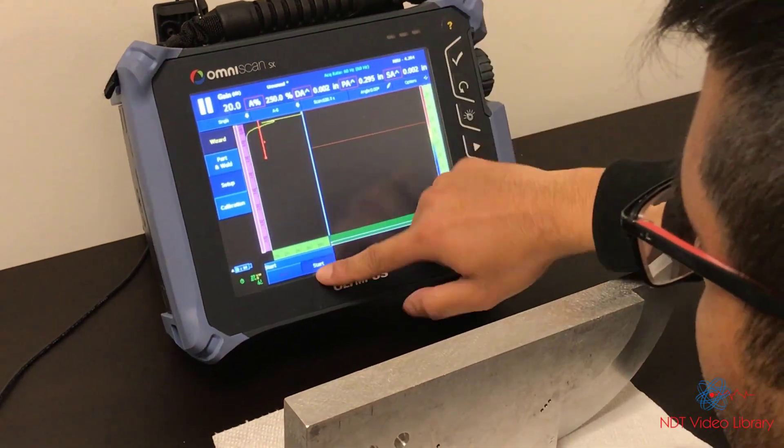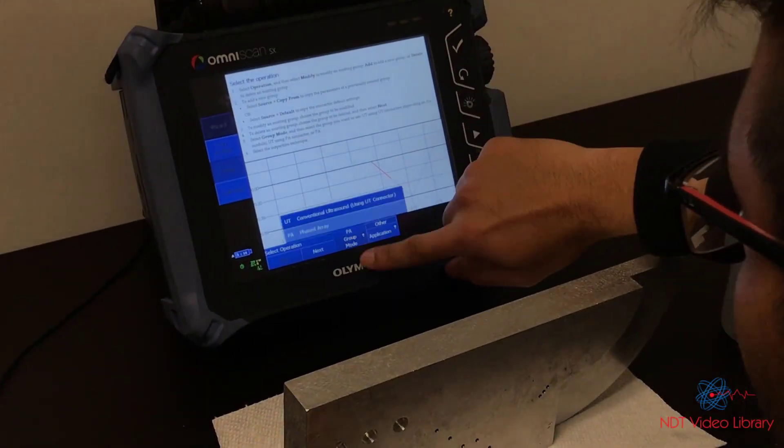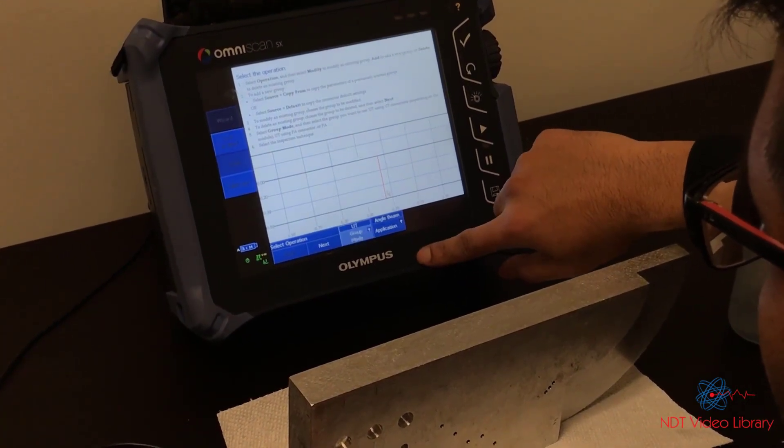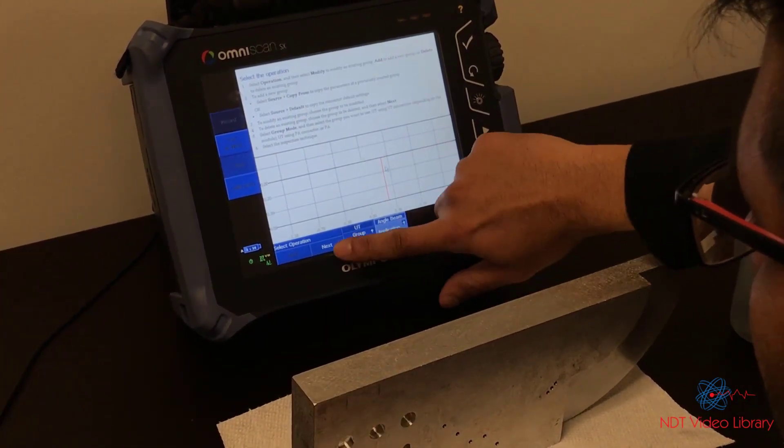Then we go to setup and start. Group mode, conventional ultrasonics, application angle beam. Next.